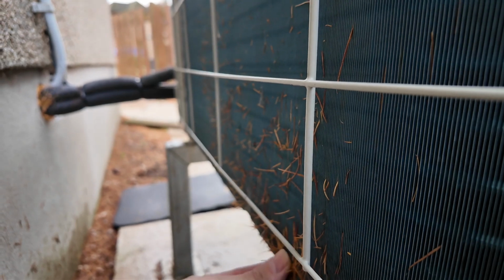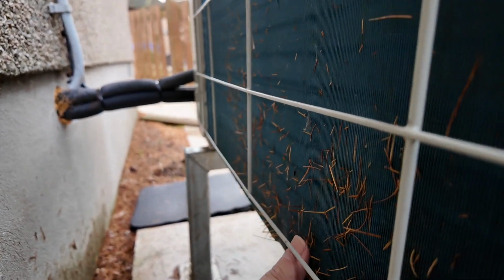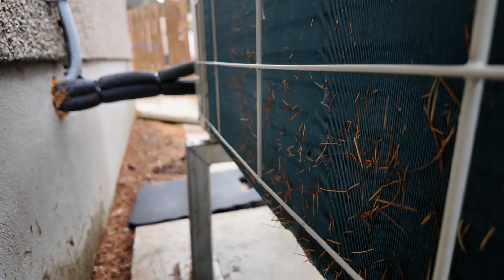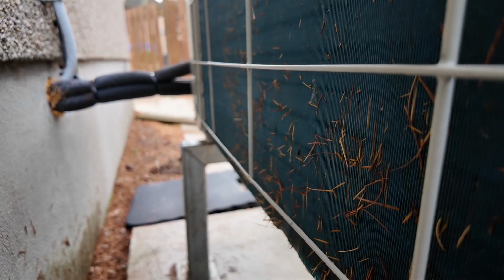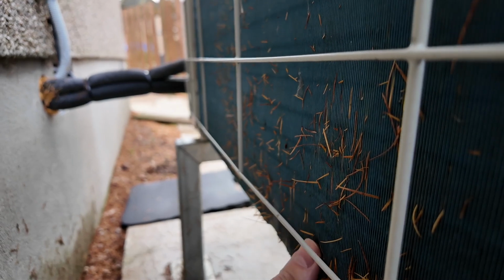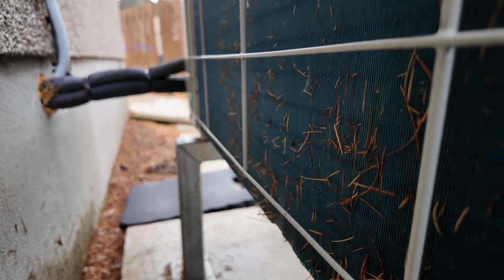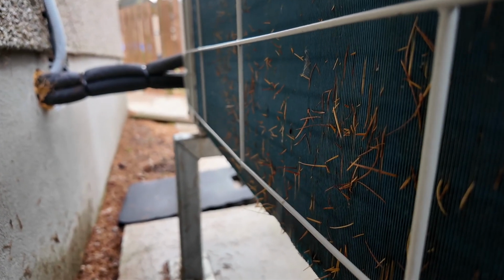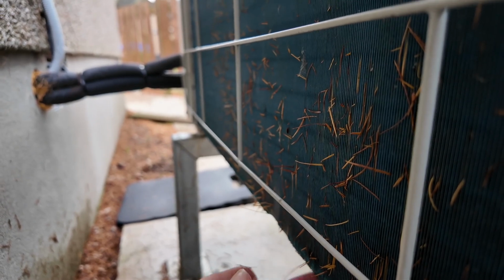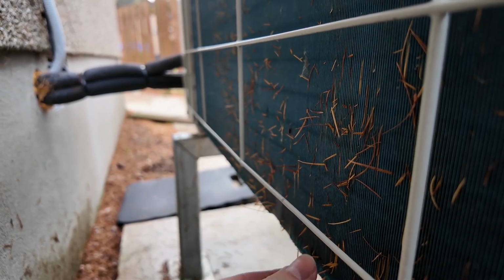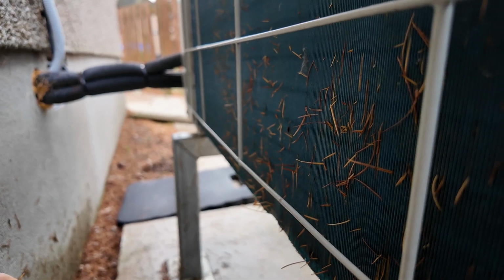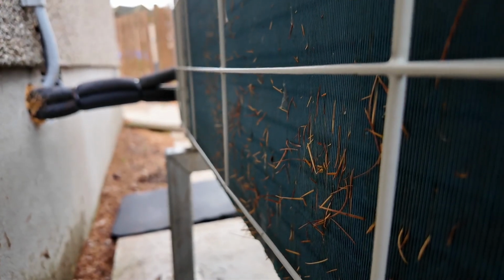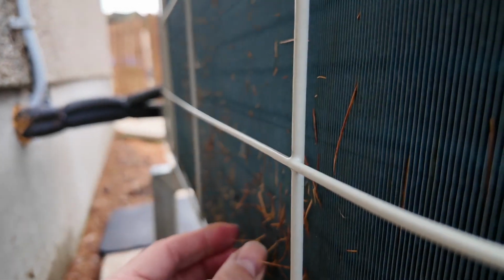You can remove a lot of it, but this is very wet. It does not react too effectively to a vacuum cleaner, as I've discovered. And the other thing you need to be mindful of is that sometimes you get a line of ice right at the bottom there, so that can make removal difficult. But here we are.